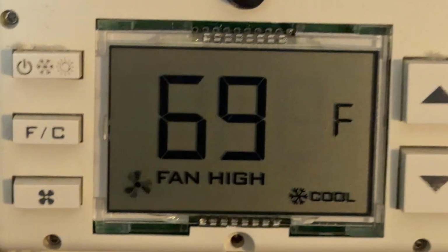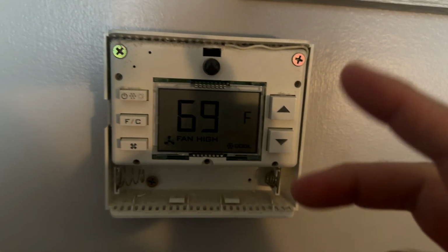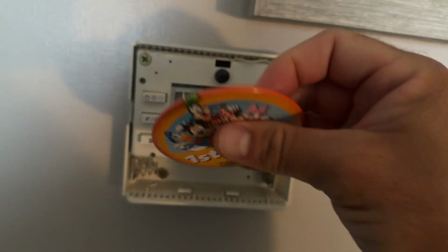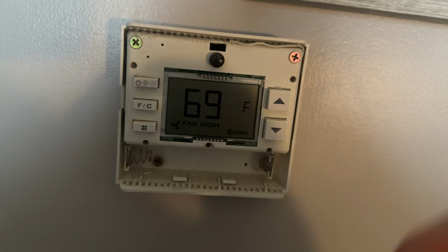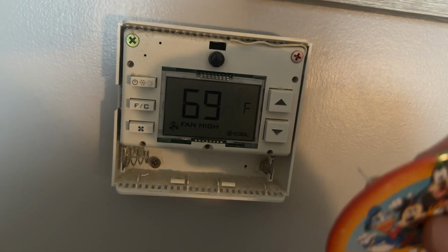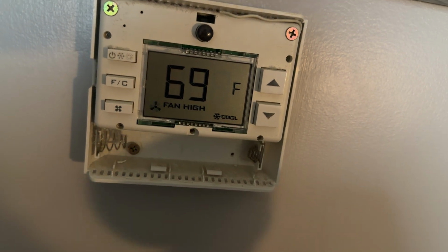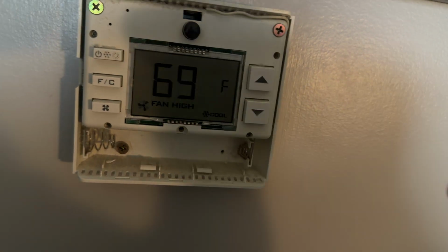So first thing we're going to do is, there's two different types of menus in here. If you do a short press on the configuration button, it gets you to one menu. Then if you do a holding press, it gets you to a different menu. First, we're going to set up the clock, because the night occupancy mode could be affected by that, and it accesses the energy conservation mode.